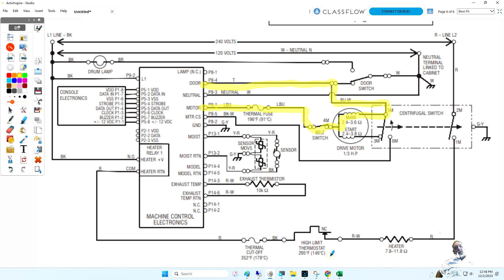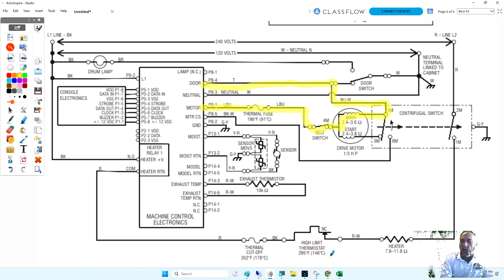Go to the 120 volts. Yes. Remember, always start with voltage if you can. The only time we don't do voltage testing is where our safety, or the safety of the machine, is at risk, like back in the day with the old Whirlpool dryers, belt driven, where you wanted to check the solenoid on the transmission for power, but that piece moved back and forth with a belt running in front of you. That's not that safe. If you were down there at the motor, you could probably do that voltage test if the drum's there and everything, but it'd be very difficult and unsafe. But if you checked voltage at P84 and P91, what must you do to check voltage there?